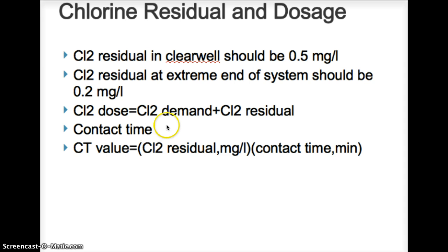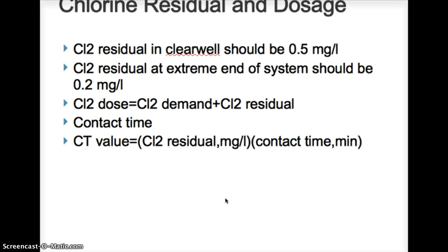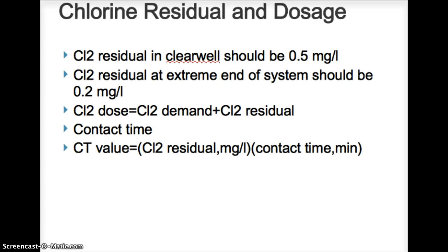Contact time is required, and that CT value, which is not the contact time, it's the CT value. Contact time, as you see here, is a factor in that. So it would be the residual, whatever your residual is at the time, times the contact time. That is your CT value. Be careful. That is something that often students get tripped up with on tests. So contact time is different than the CT value itself.